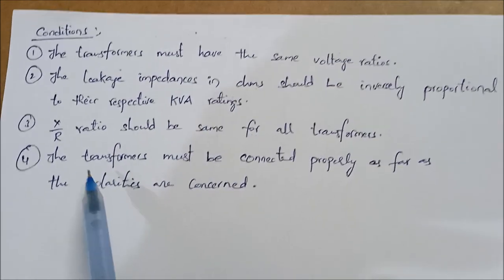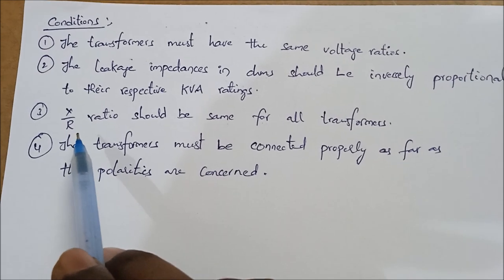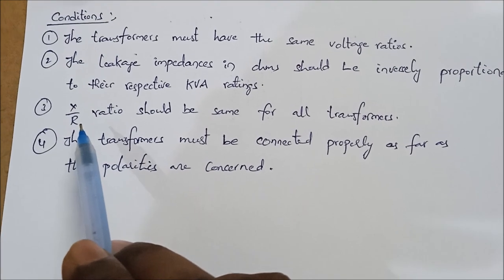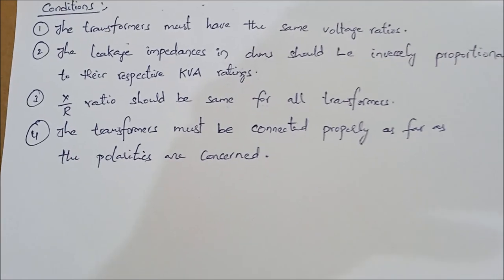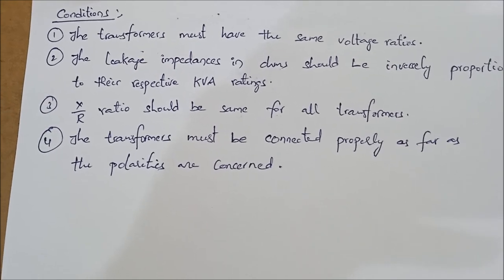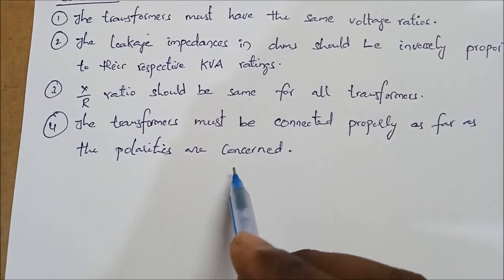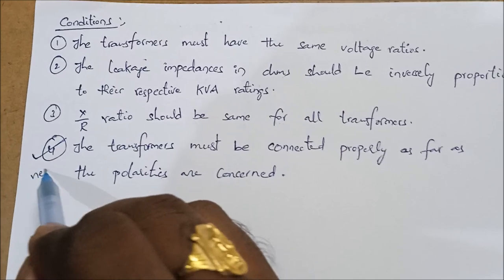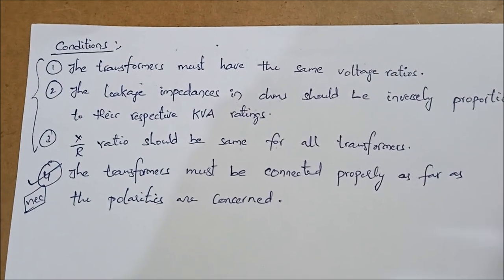We will understand the second point later. The third condition is that the X/R ratio should be the same for all transformers. In impedance ZA and ZB, X is the reactance and R is the resistance, so the X/R ratio of transformer A should equal the X/R ratio of transformer B. The fourth condition is that the transformers must be connected properly as far as polarities are concerned. The fourth point is the necessary condition, while the first three are only desirable conditions.